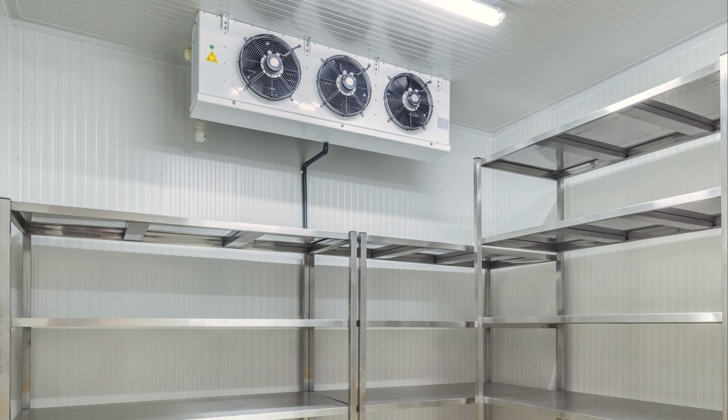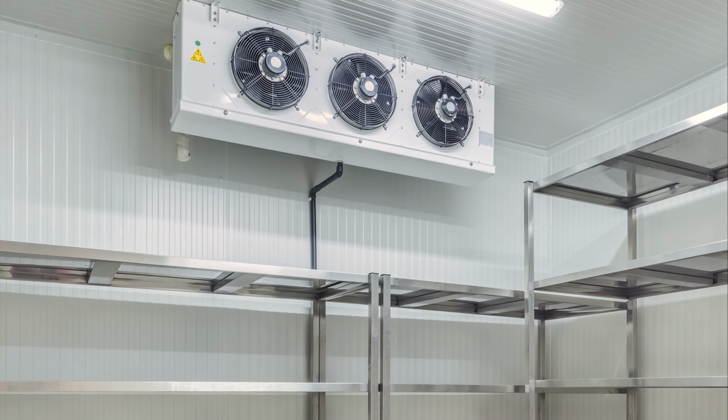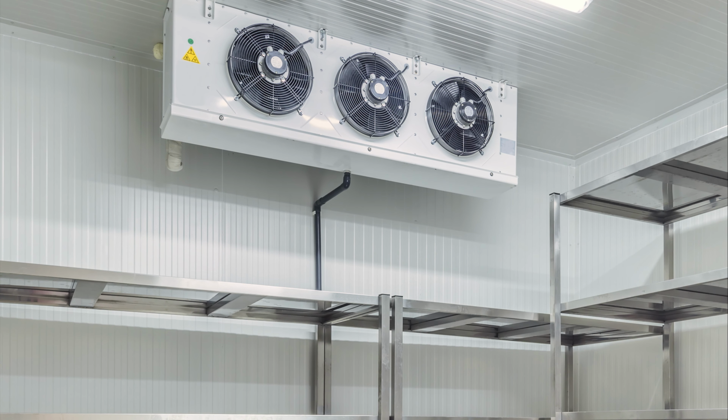Evaporators can be found in the chiller or cold room. This is where the refrigerant receives heat from the items being cooled. The best way to improve the energy efficiency here is to regularly check the evaporators and get the coils cleaned by a technician. If there's any significant buildup of ice, this could indicate a problem.